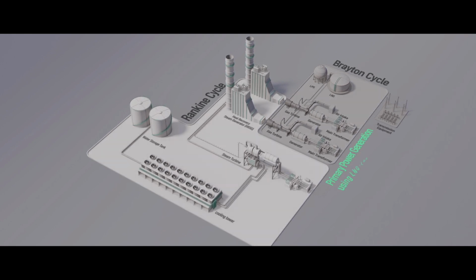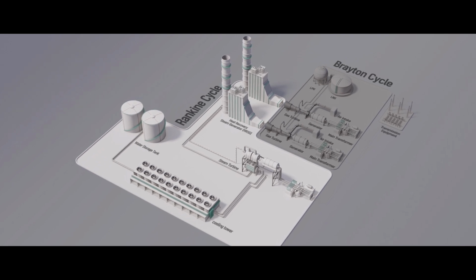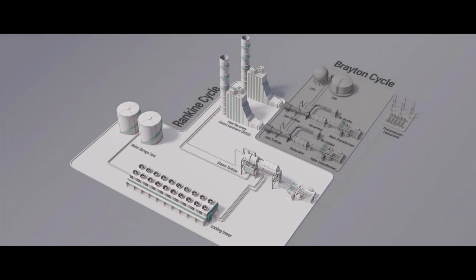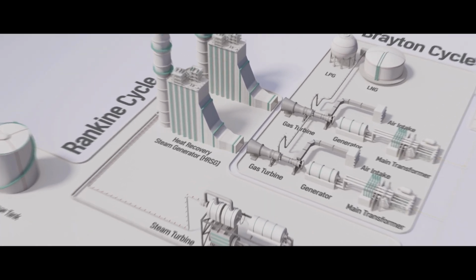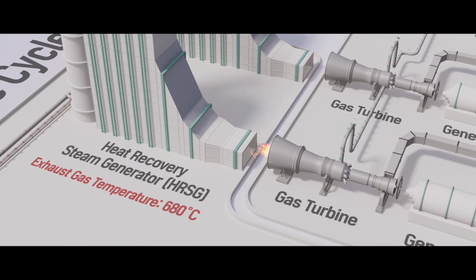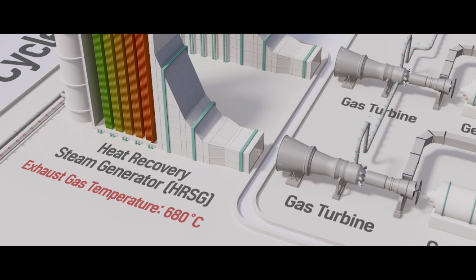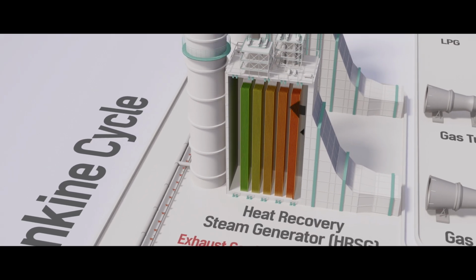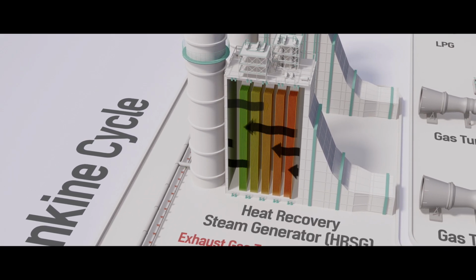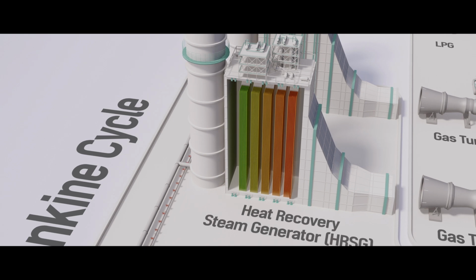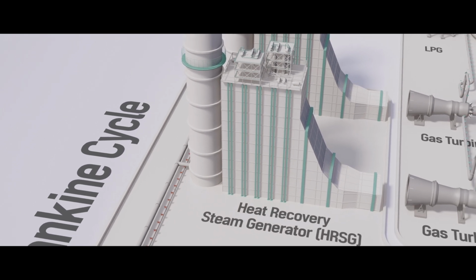Instead of releasing the hot exhaust gas, we capture its thermal energy to produce even more electricity. The exhaust gas reaches temperatures of around 680 degrees Celsius. Inside the heat recovery steam generator, this heat is used to boil water, producing high-temperature, high-pressure steam.